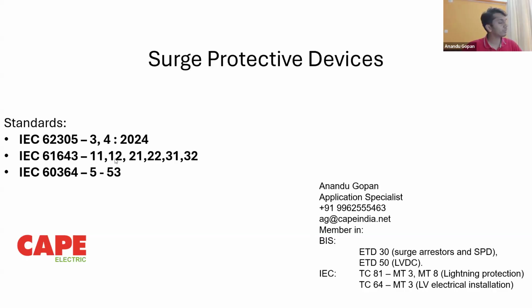Basically 11 and 12 are for low voltage SPDs, power line SPDs. 11 is for testing, 12 is for usage: what is the application, and how to select and erect an SPD. 21, 22 is for telecommunication or data line SPDs. 21 is for testing, 22 is for selection and erection of an SPD. 31, 32 is for PV SPDs; 31 is for testing, 32 is for the application. And parallelly, for low voltage electrical installation, IEC 60364 or our IS 732, you can find in 553 how to use an SPD.